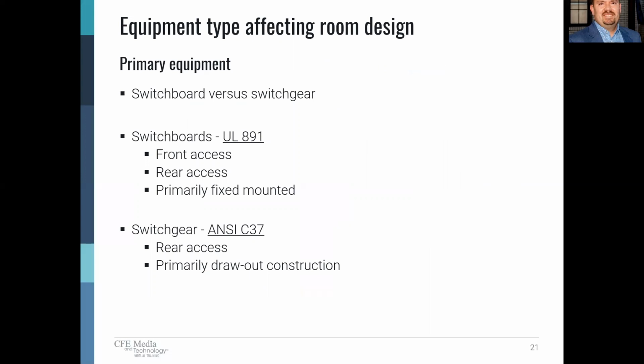So we touched on this a little bit earlier, but I wanted to talk about some of the differences between the primary equipment that we normally see, the types that we see. The primary equipment is often a switchboard or a switchgear lineup where the service comes into the building. Switchboards generally are front access. They can also require rear access depending upon the type, but generally they're front access and they can be placed against the wall. And the overcurrent protected devices in the switchboard lineup are fixed in place.